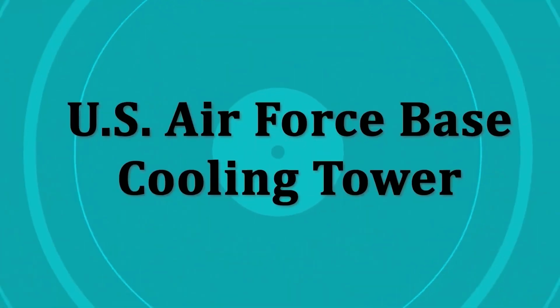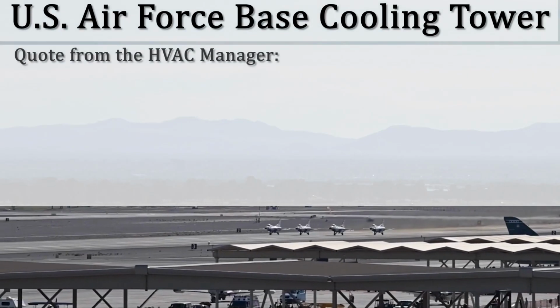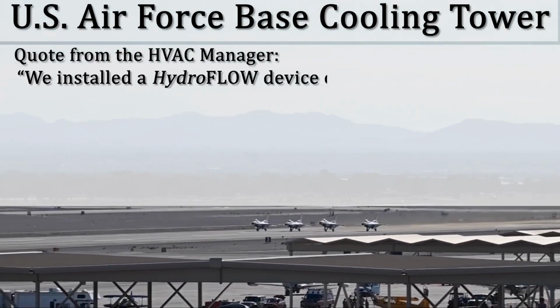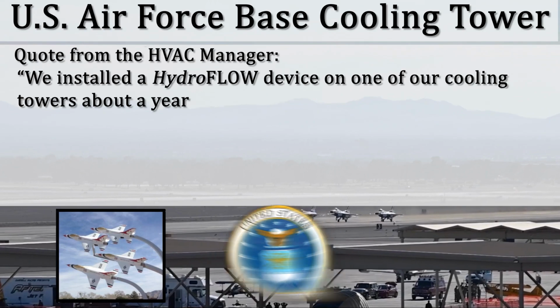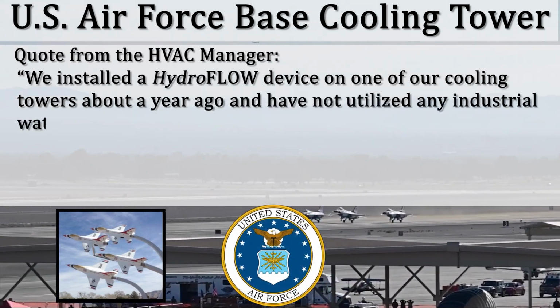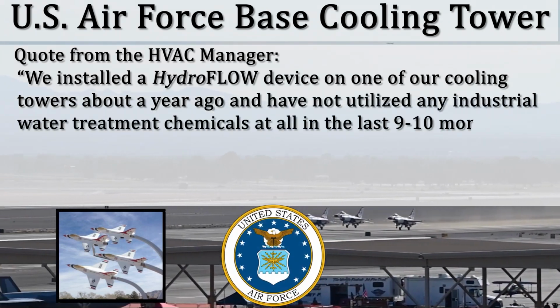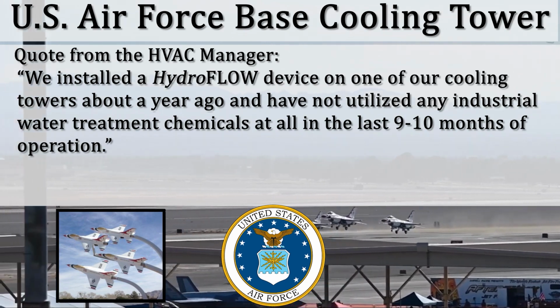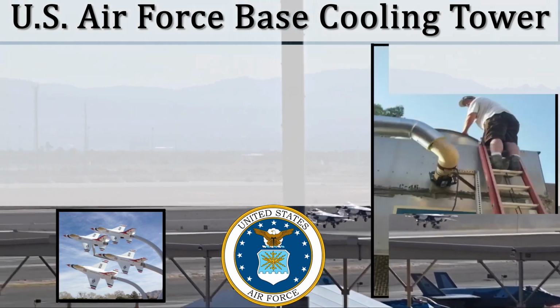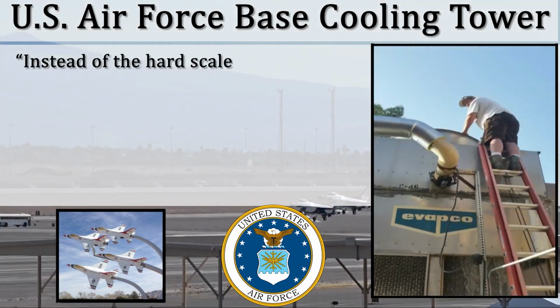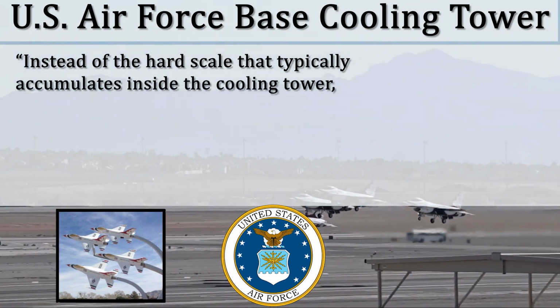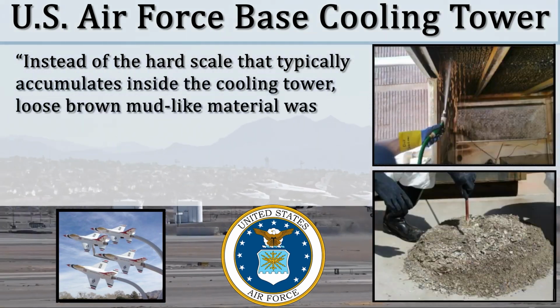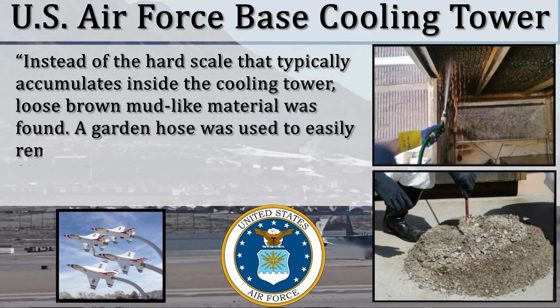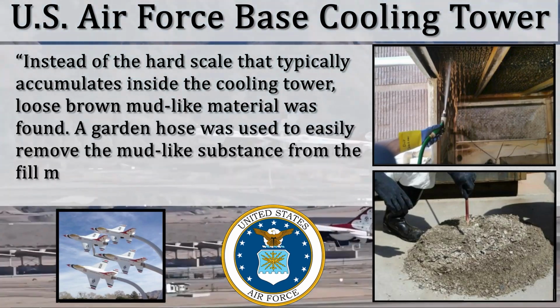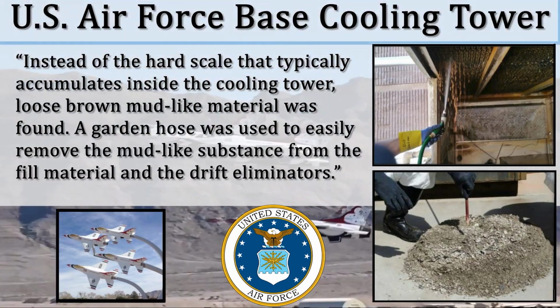U.S. Air Force Base cooling tower. Quote from the HVAC manager at the base: "We installed a HydroFLOW device on one of our cooling towers about a year ago and have not utilized any industrial water treatment chemicals at all in the last 9 to 10 months of operation. Instead of the hard scale that typically accumulates inside the cooling tower, loose brown mud-like material was found. A garden hose was used to easily remove the mud-like substance from the fill material and the drift eliminators."